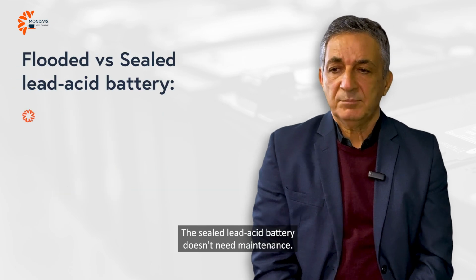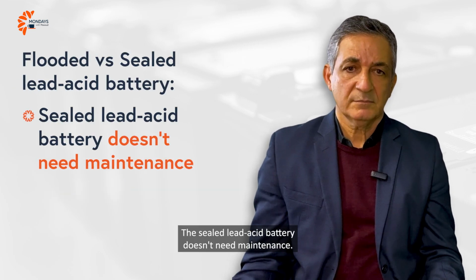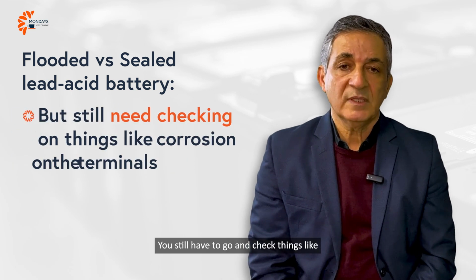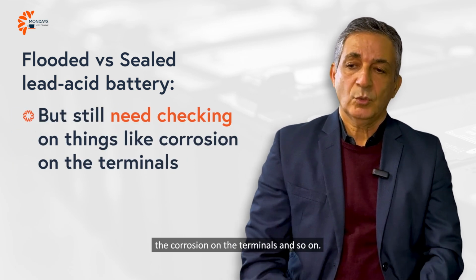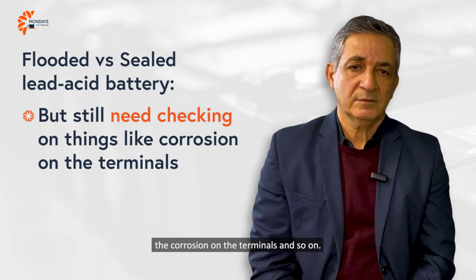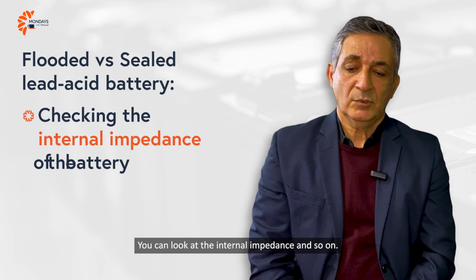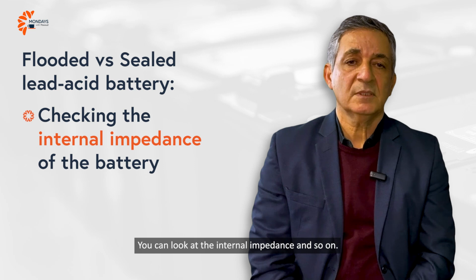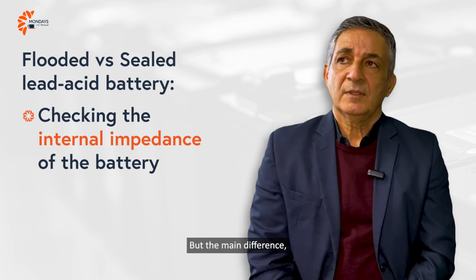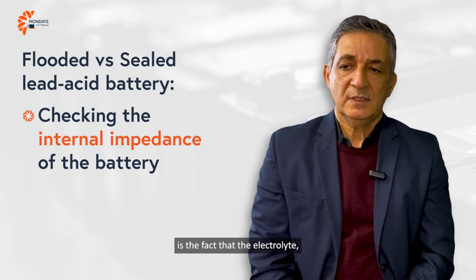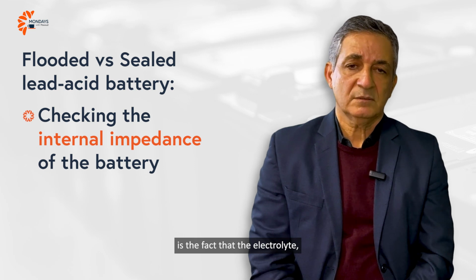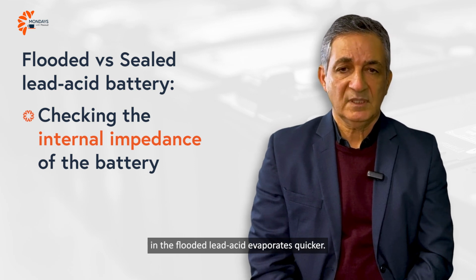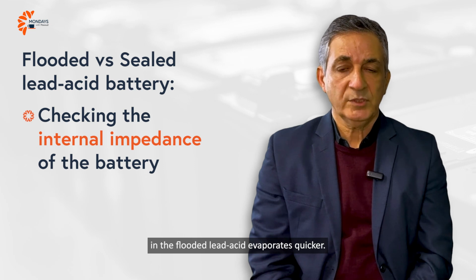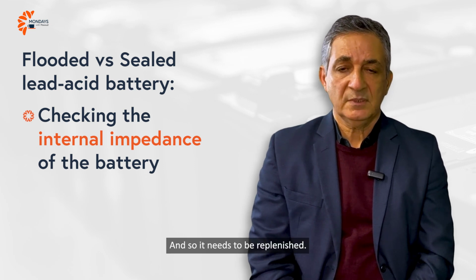The sealed lead-acid battery doesn't need maintenance, right? You still have to go and check things like the corrosion on the terminals and so on. You can look at their internal impedance and so on. But the main difference is the fact that the electrolyte in the flooded lead acid evaporates quicker, and so it needs to be replenished.